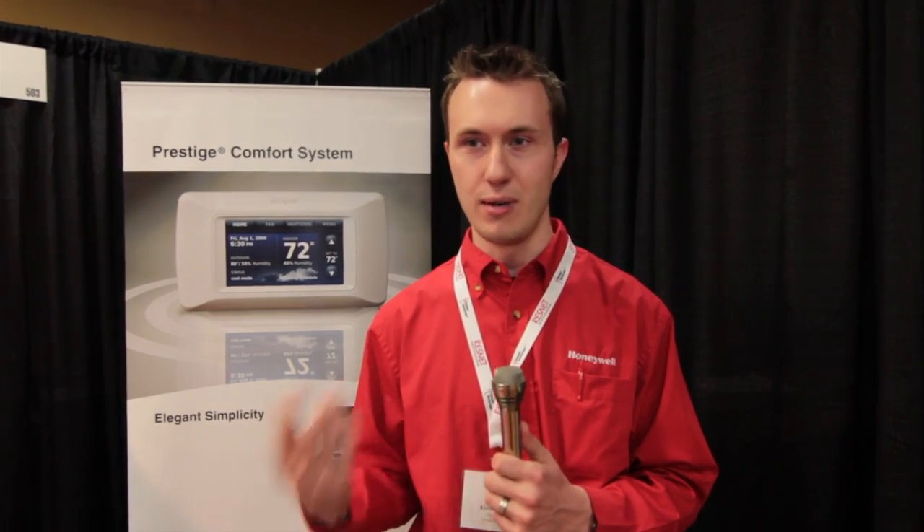In addition to our Prestige IAQ, we have two other products that are helpful depending on the situation. We have a product called our W8150, which is a very simple but very powerful ventilation control. It still ventilates based on the ASHRAE 62.2 standard, and in the setup it's just a couple of dials that the contractor sets to enter the square footage of the house, the number of bedrooms, and the capacity of the ventilation product. It will automatically control that ventilation device to meet ASHRAE 62.2 code without needing to connect it to the thermostat if you don't want to.